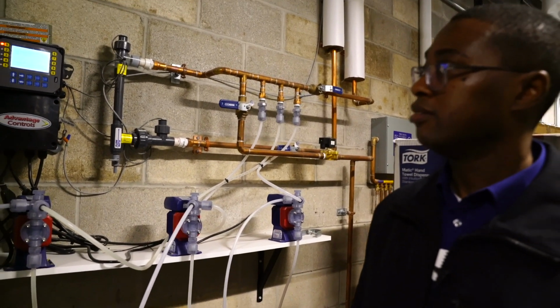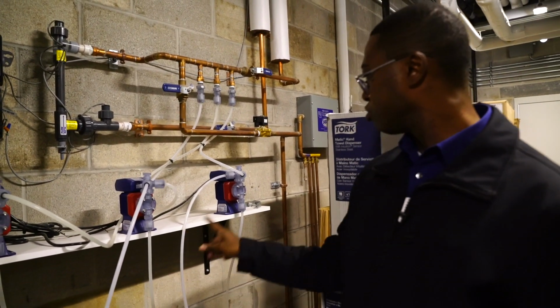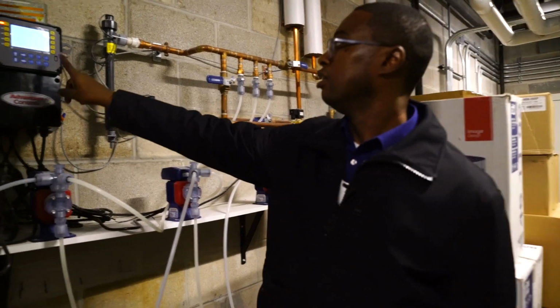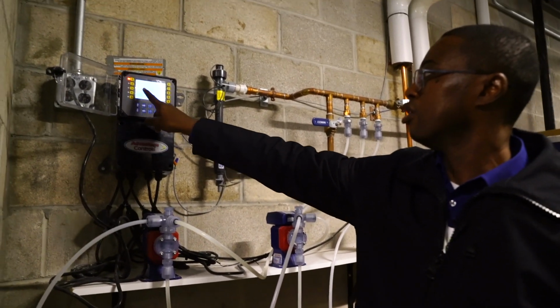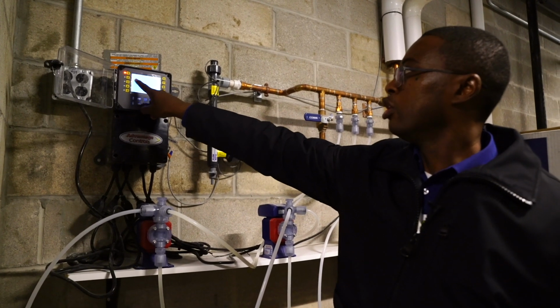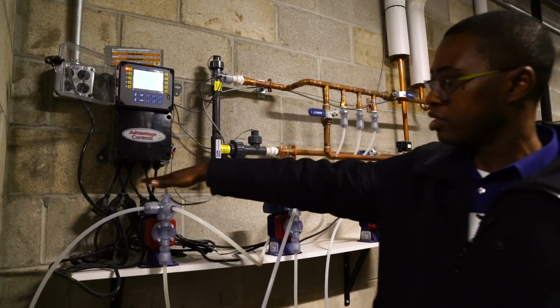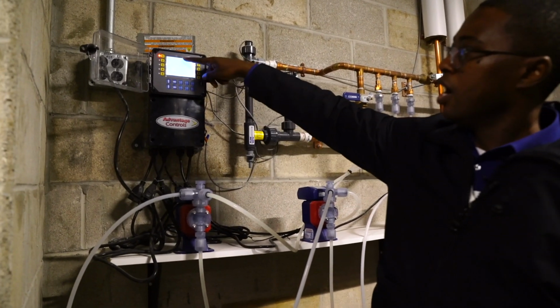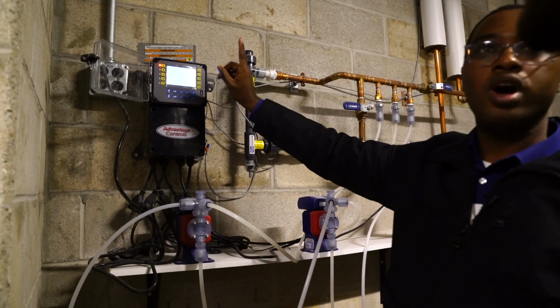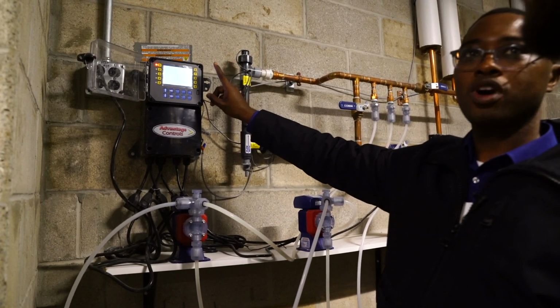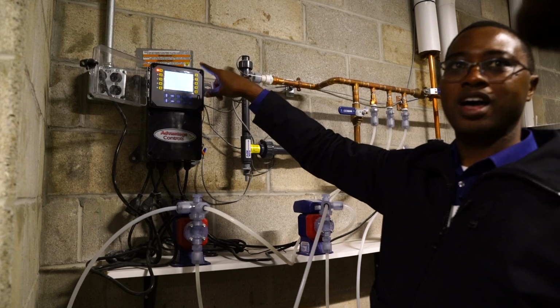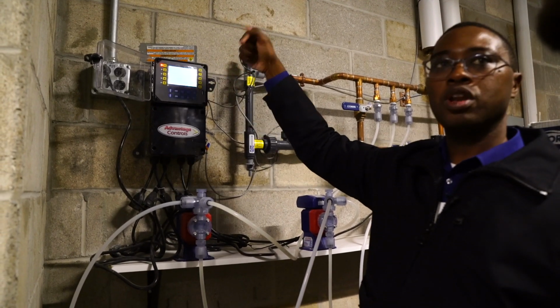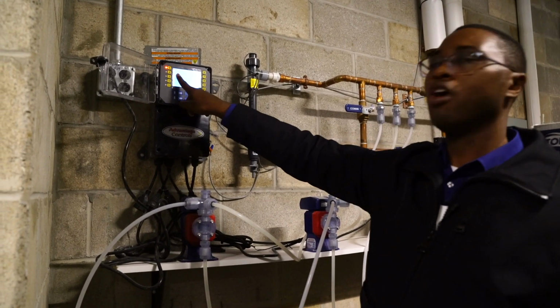Did you hear the pumps running? Okay, when they were kicking on, that number will start to drop, as you see right now. So we have relays, right—1, 2, 3, 4, 5 relays. All the relays are off except for one, because of that 5,000 reading. If that number was below 5,000, this would be off as well.